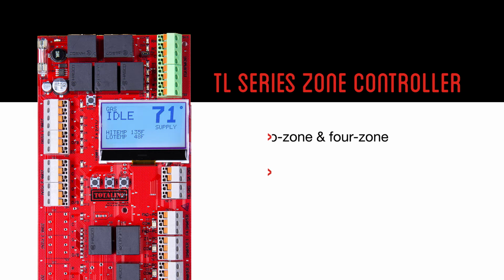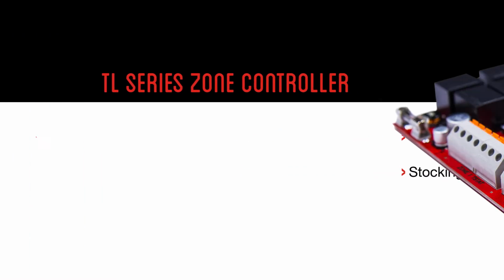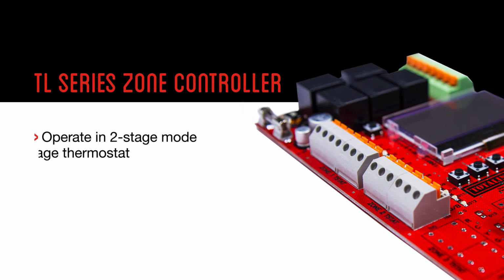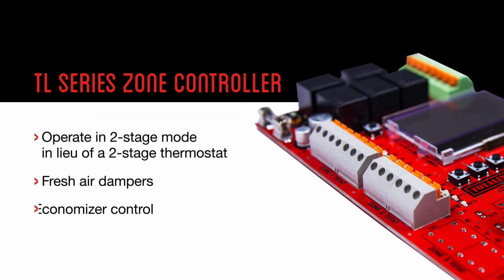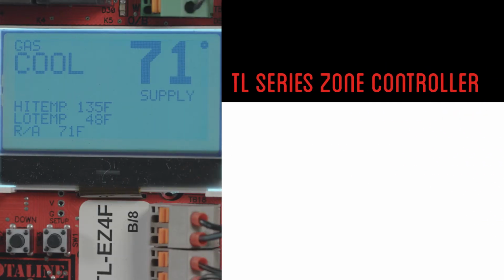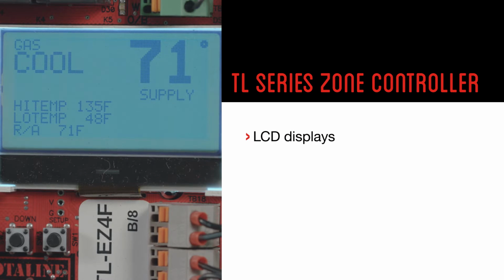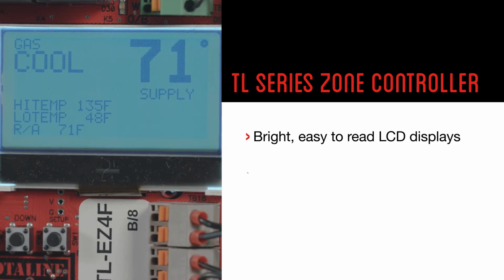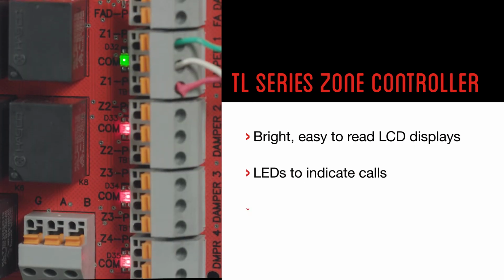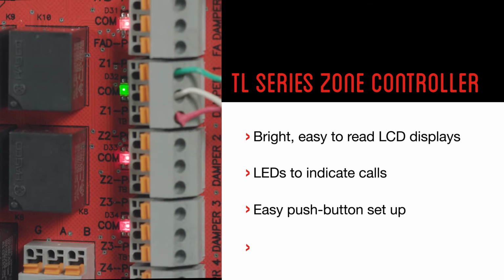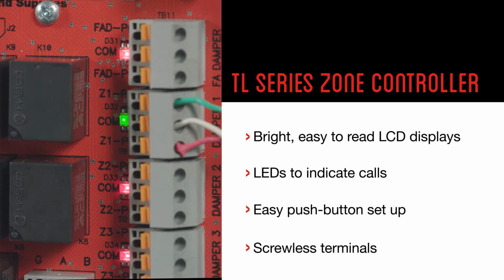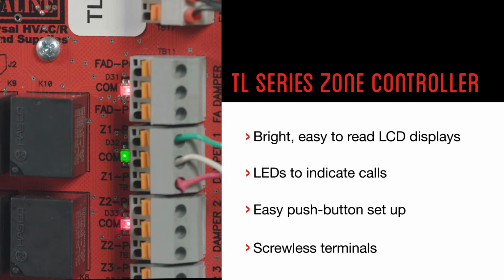With just 2 controllers covering the majority of the market, we've made stocking simple for you. Controllers can operate in 2-stage mode in lieu of a 2-stage thermostat. Features include fresh air dampers, economizer control, expansion board options, and more. All Totaline TL Series zone controllers feature bright, easy-to-read LCD displays, LEDs to indicate calls, easy push-button setup, and screwless terminals for ease in setting up and troubleshooting.